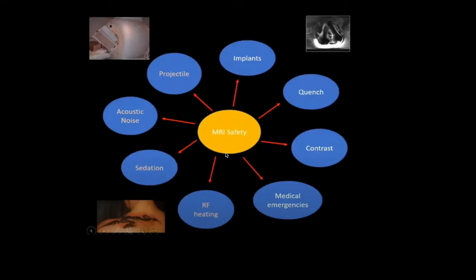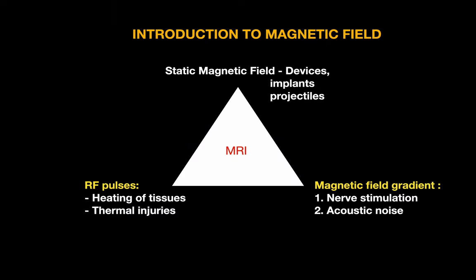MRI safety is divided into implants, quench, contrast, medical emergencies in MRI, RF heating, sedation, acoustic noise, and projectiles. Magnetic field can be divided into three parts: static magnetic field, magnetic field gradients, and radiofrequency pulses. Static magnetic field can cause device implant or projectile-type injuries; magnetic field gradients can cause nerve stimulation or acoustic noise; and radiofrequency pulses can cause heating of tissue and thermal injuries.